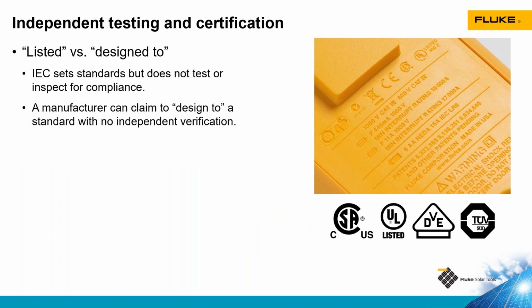Now at Fluke, we design our tools to certain specifications, the category and voltage ratings for the tool, and then we have the tool sent off to a third-party listing agency who tests it and then lists the tool to that standard. So they look at the standard that we're designing the tool to and then actually test it to that standard and make sure it meets those requirements. Not all companies do that. Some will say that it's quote-unquote designed to a standard, but it's not actually tested by a third party, so we don't know if that will actually meet those requirements or not.